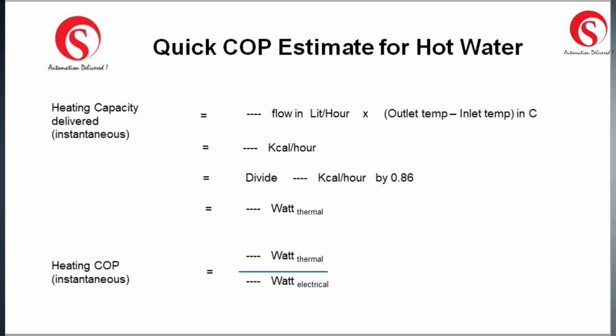Whenever we are calculating the heating time, overall energy consumption and the COP, we always take the overall integration of this entire heating time, then we work out what the COP is. We don't go by any instant number. We calculate how much energy has been consumed during the total heating time. So if our electrical panel has an energy meter, it automatically helps to see what the COP of the heat pump is to raise a particular volume in liters of a degreasing solution tank, or any other tank, from T1 to T2. So this is something very interesting.